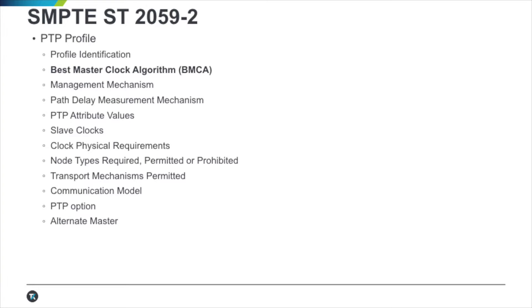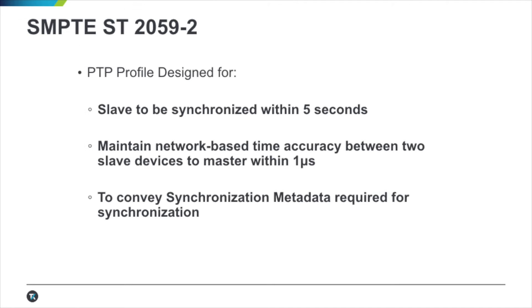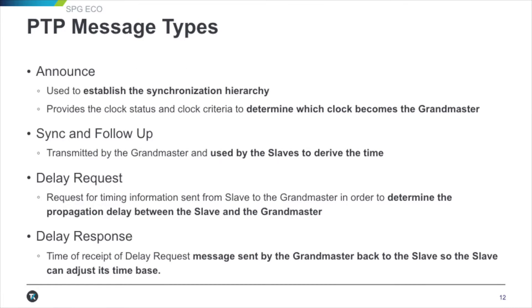Dash-2 gets a little bit deeper, talking about the best master clock algorithm — the BMCA — which is how the network determines which clock is the master that all other clocks defer to. PTP profiles are designed so a slave should be synchronized within five seconds of connecting to the network. The accuracy of the network needs to be within one microsecond. There is synchronization of metadata so all devices know the signal latency between point A and point B. PTP message types: Announce establishes the synchronization hierarchy and determines which clock becomes the grandmaster.